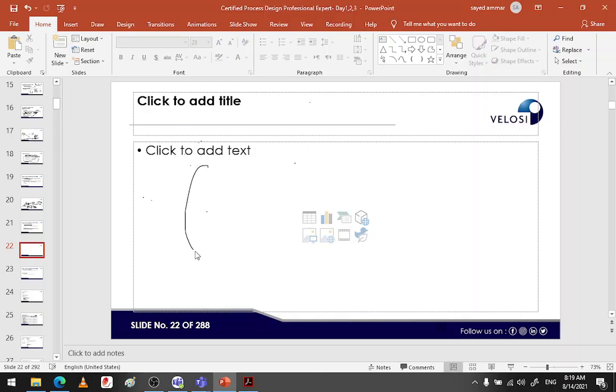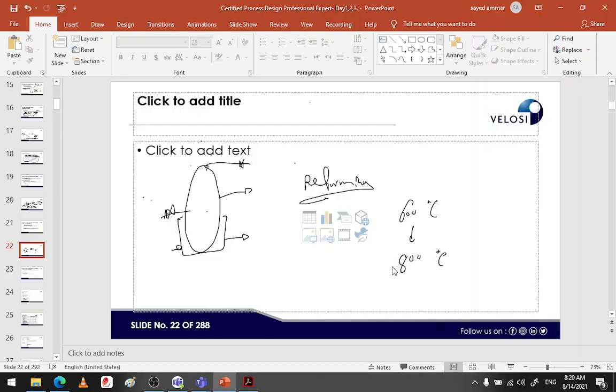Here is the reformer. Here is the outlet of the reformer. And here is the jacket which has the cooling water. Cooling water in, cooling water out. What I am trying to say is that normally the reforming reaction runs at around 600 C. It can reach 800 C. Also, if you are ignoring it, Muhammad, it can reach 1000 very easily.